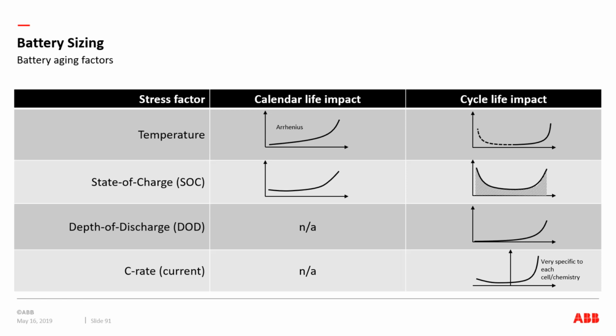In short, what you effectively end up doing is oversizing the battery or the amount of energy you need, depending. Probably the biggest factor is the number of cycles. For example, if you have one cycle per day, meaning one charge per day, you'd typically size a battery for a 10-year life—10 years, one cycle a day, that's 3,600 cycles.